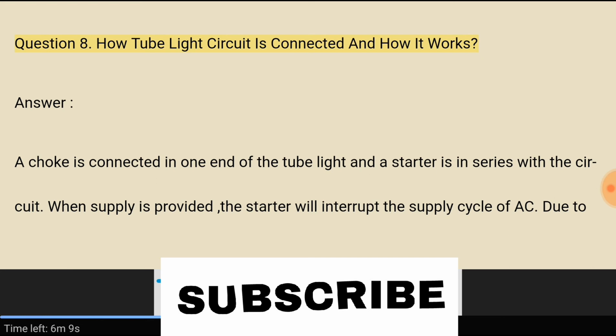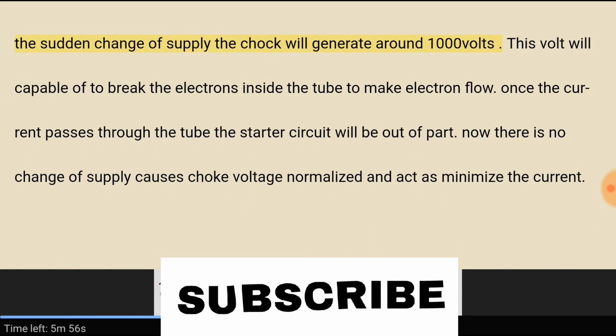Question 8. How is a tube light circuit connected and how does it work? Answer. A choke is connected at one end of the tube light and a starter is in series with the circuit. When supply is provided, the starter will interrupt the supply cycle of AC. Due to the sudden change of supply, the choke will generate around 1000 volts. This voltage is capable of breaking down the gas inside the tube to make electrons flow. Once the current passes through the tube, the starter circuit is out of the picture. Now there is no change of supply, so the choke voltage normalizes and acts to minimize the current.